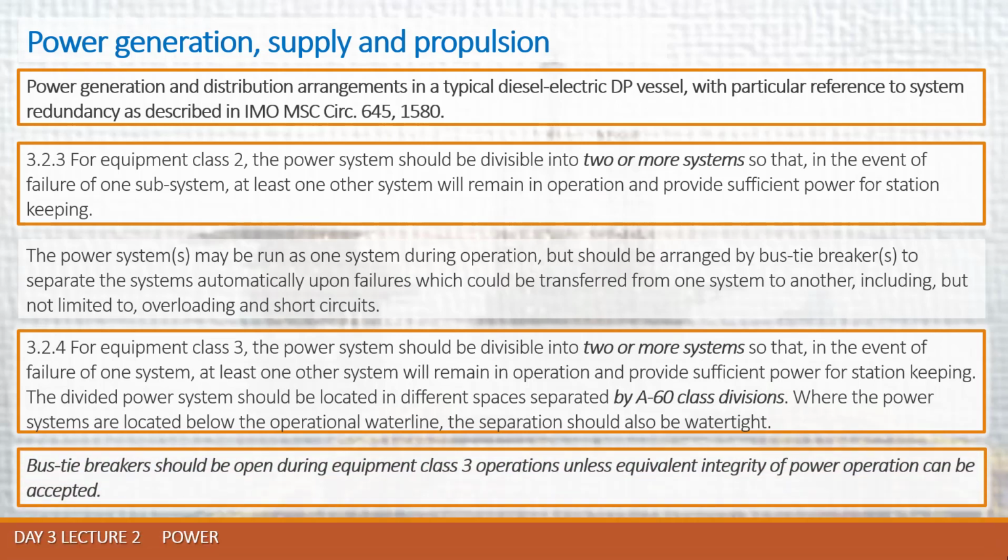So it depends on your type-specific design. The bus tie breaker may be closed or open, and sometimes we have it closed as a concept of design. The main reason is we would like to share the loads in an equal manner between all running generators. But such concepts have fast-reaction breakers, which in the event of a short circuit will be opened automatically in a very fast manner.